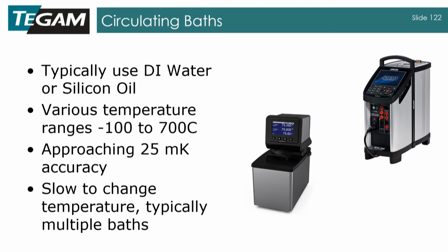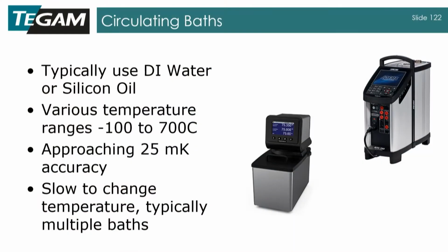Also, when you're using baths, you've got a lot of fluid to change, so you don't typically change the temperature often. If you need to measure several points, you'll have as many baths as you need points, and then you can take your sensor or your instrument, if you're doing both, together all the way through that range. So the dry blocks and the circulating bath are both examples of sourcing and measuring temperature directly.